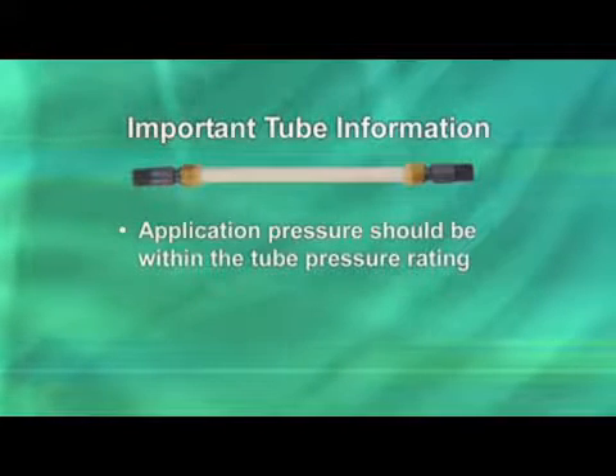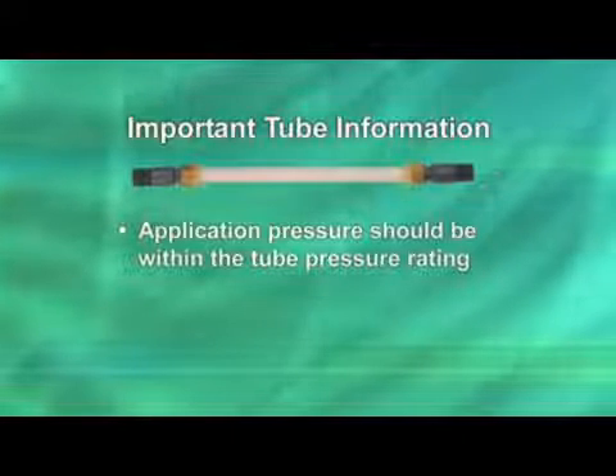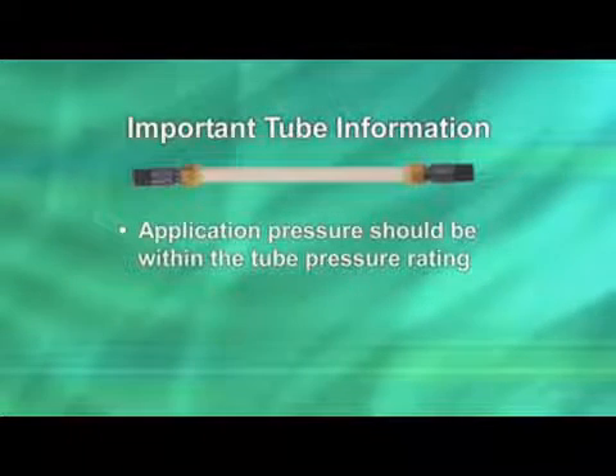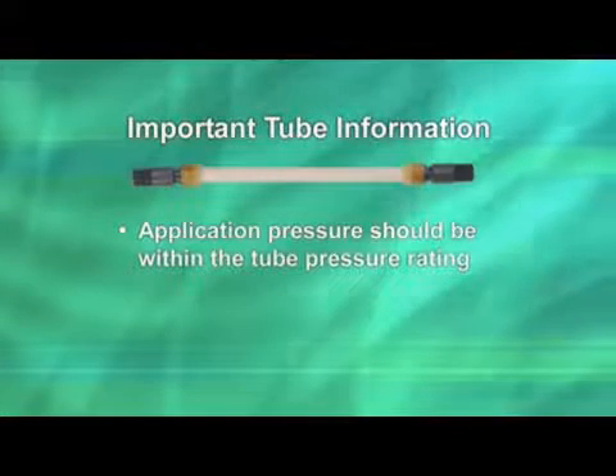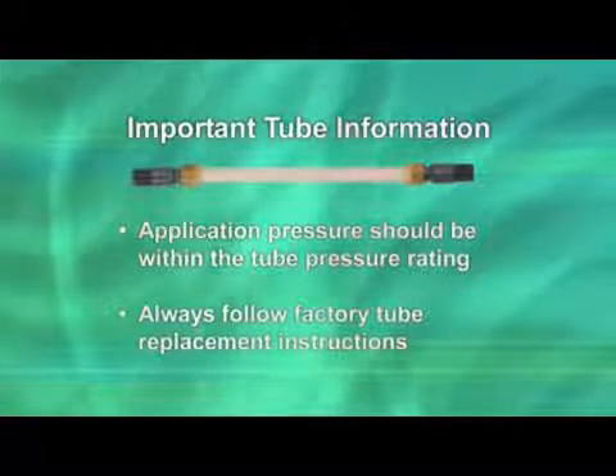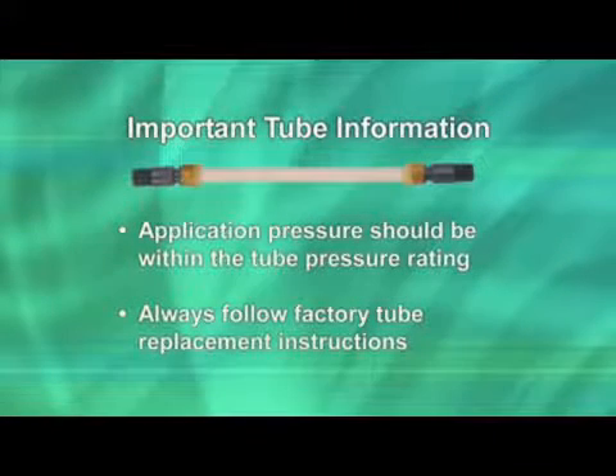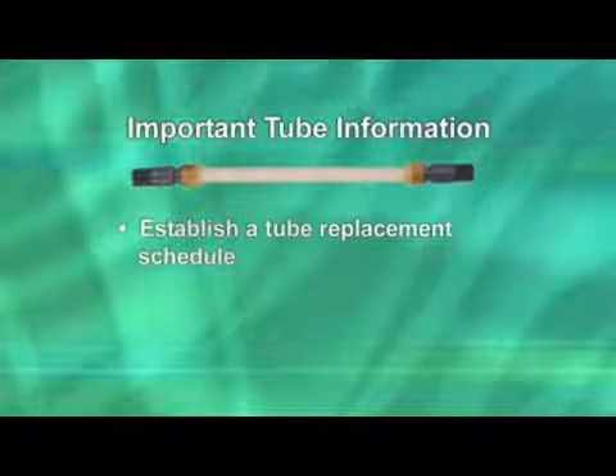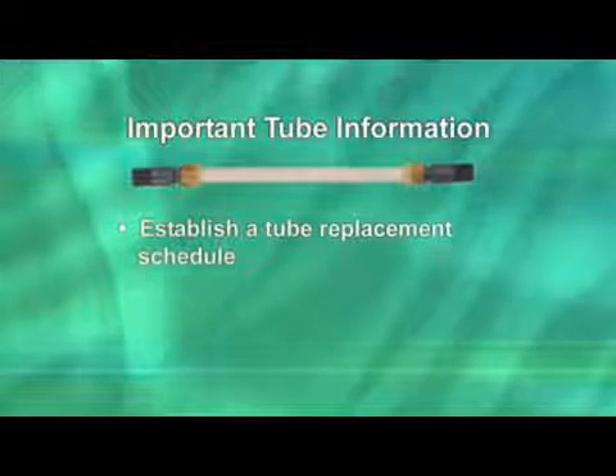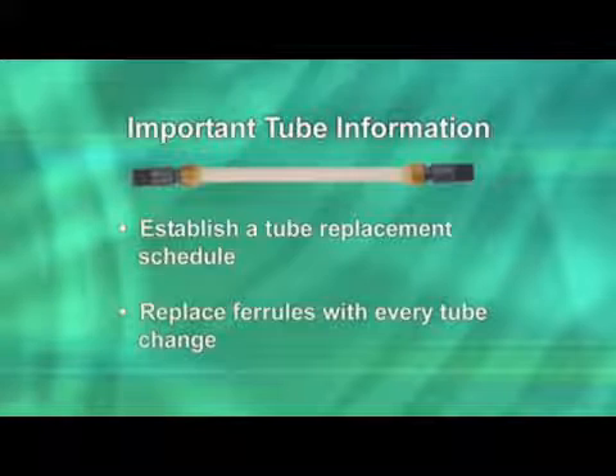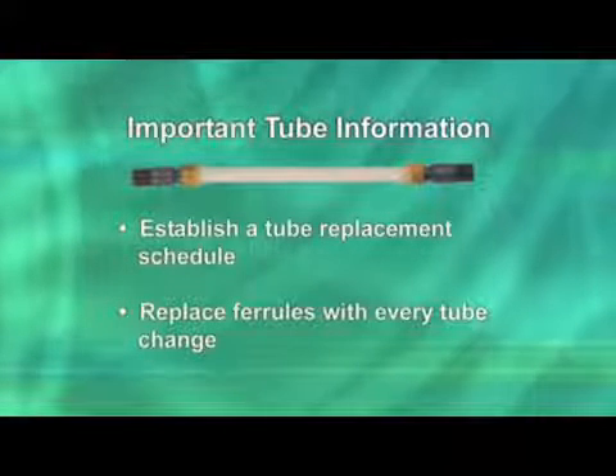In summary, here is some of the most important tube information. Confirm the application pressure rating is within the pump tube pressure rating, and note that the tubes rated 26 to 100 psi require the use of a check valve. Always follow factory tube replacement and centering instructions in the manual. Schedule a tube replacement at regular intervals according to the needs of the specific application. Replace ferrules with every tube change.